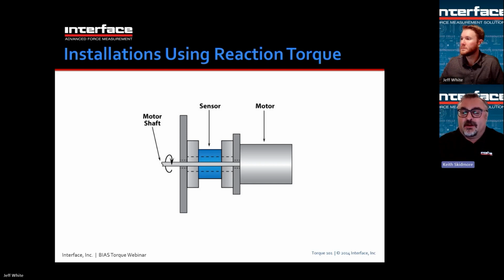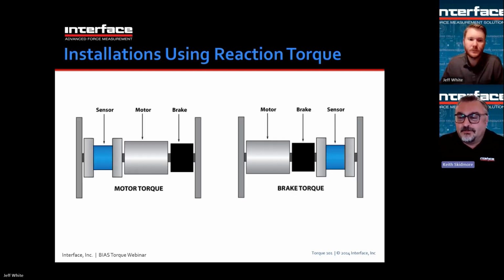The housing of the motor is attached to the torque sensor, and as the shaft is loaded, the housing of the motor tends to want to spin in the opposite direction of the shaft, and it's held from spinning using the torque sensor. It's a reaction torque. That's why we call these reaction torque sensors, as well as static torque sensors. So the reaction of the motor housing is equal and opposite to the torque in the motor shaft. Very common approach. This is much simpler than using a rotary torque sensor and can be a preferred approach depending on the application. Next slide, please.